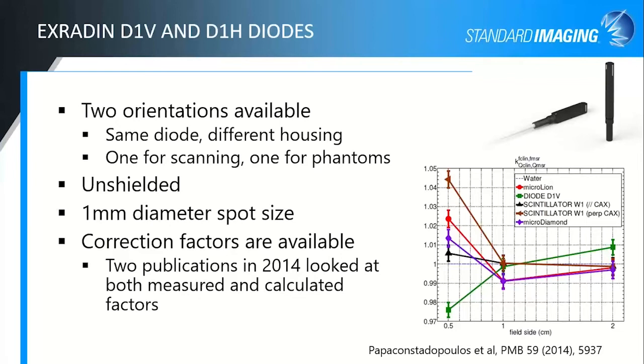So for our diodes, the D1V and the D1H, it's the same diode, just in 2 different orientations. So the horizontal version is really designed for use in a plastic phantom. The vertical version is designed for use in scanning, so you're end on to the beam here. But inside, it's exactly the same diode. They're unshielded, and they have a 1 millimeter diameter spot size, and there are some published correction factors available for these. There's one from Papaconstadopoulos from 2014. I think there are a few others on our website. I didn't list them here, but this image is from that publication, looking at correction factors for the D1V, as well as the scintillator, actually.